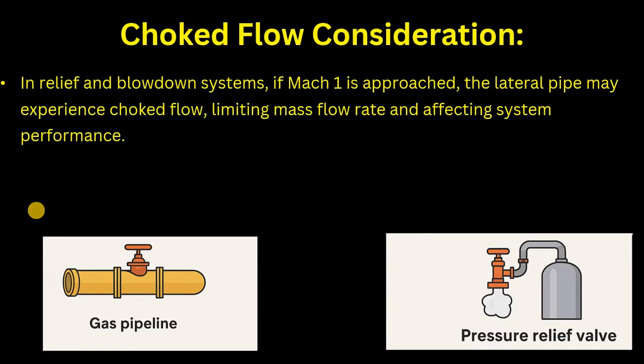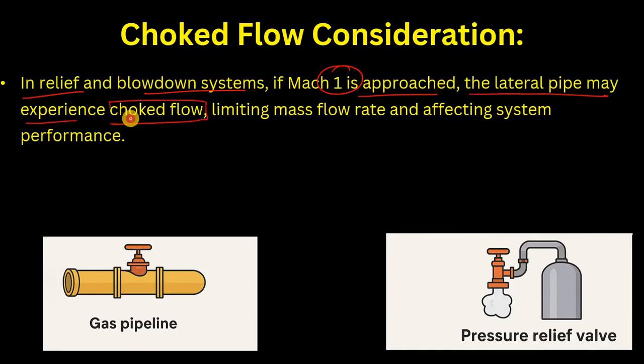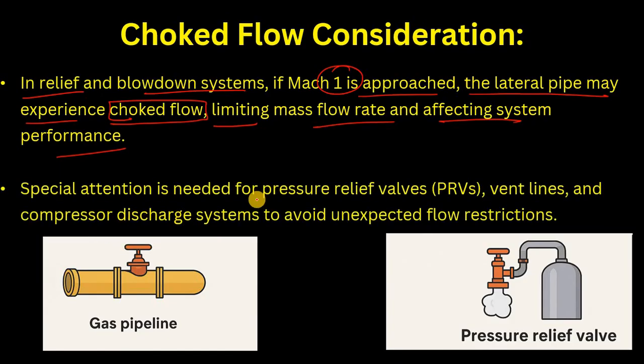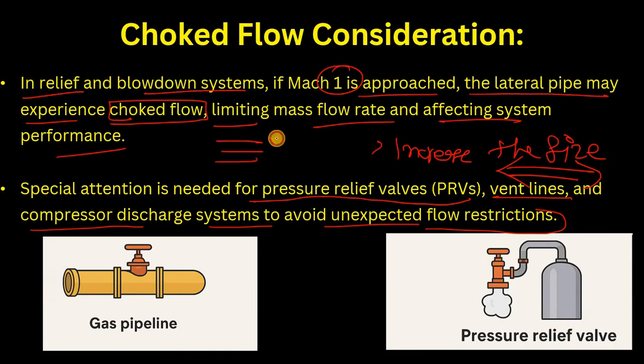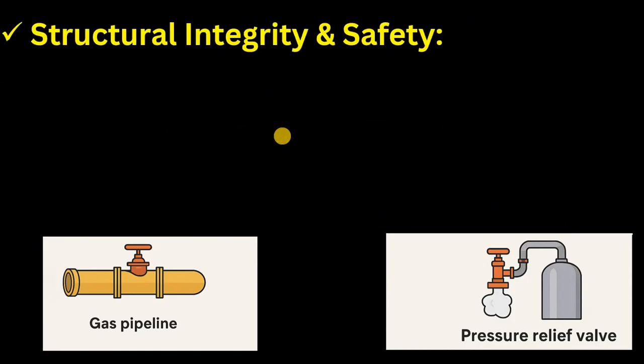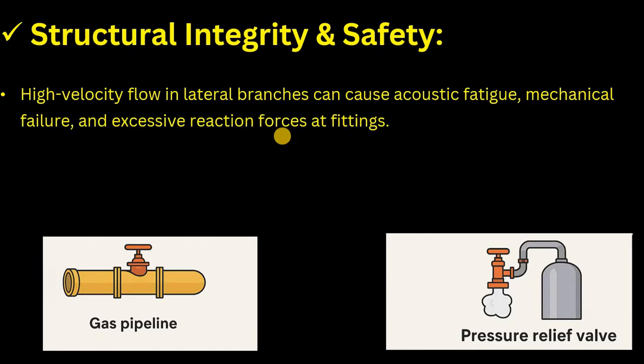In relief and blowdown systems, if the Mach number approaches one, the lateral pipe may experience choked flow, limiting mass flow rate and affecting system performance. Special attention is needed for pressure relief valves, vent lines, and compressor discharge systems to avoid unexpected flow restrictions. In such cases, we typically increase the pipe size or create line segments with successive reducers — for example, stepping from 3-inch to 2-inch to 1-inch.